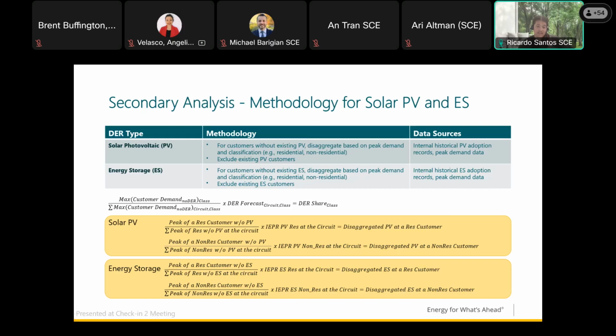I'll go through one of them. For a residential solar PV customer, this is the ratio of the peak of a residential customer without PV over the summation of residential customers without PV at that circuit. We then multiply that ratio by the IEPR amount of PV at that circuit. This gets you the disaggregated PV for the residential customer. That bottom formula within the same yellow bubble is the same, but for a non-residential customer. Energy storage follows that same equation.